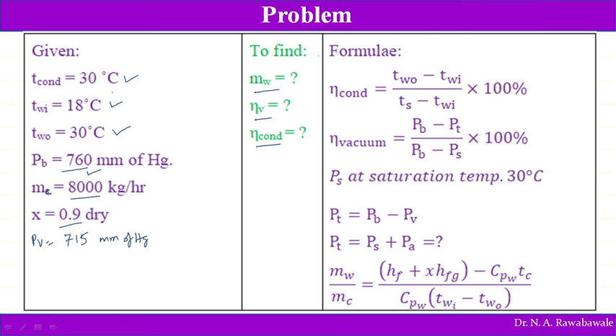Condenser temperature is 30°C and the condensate temperature is not separately given, meaning there is no under-cooling. The water outlet temperature equals the condenser temperature (30°C), so the condenser efficiency is 100 percent — an ideal case. PS can be taken at 30°C from steam tables. PB − PT over PB − PS gives vacuum efficiency.